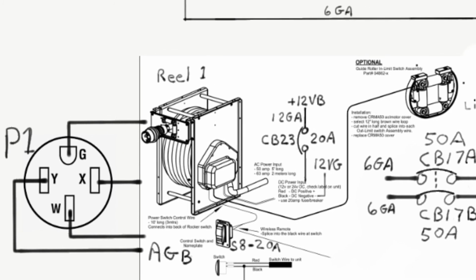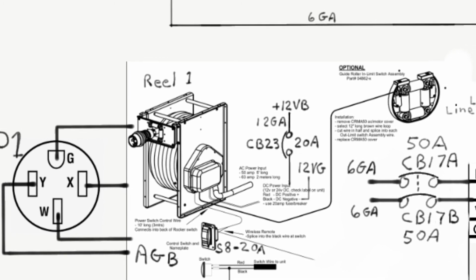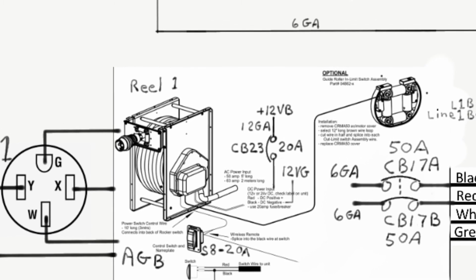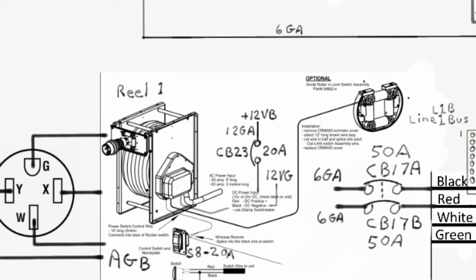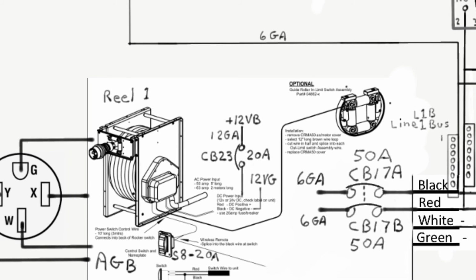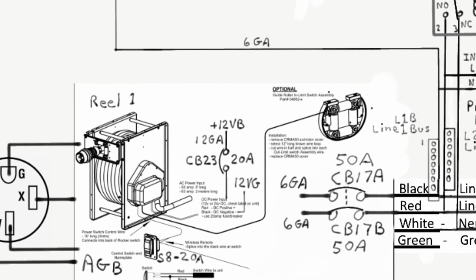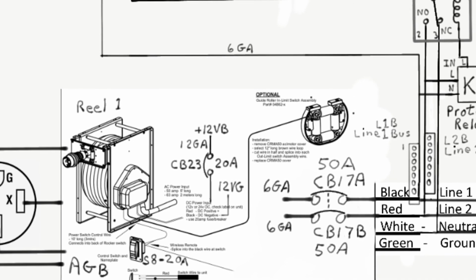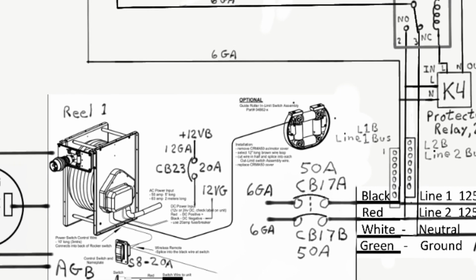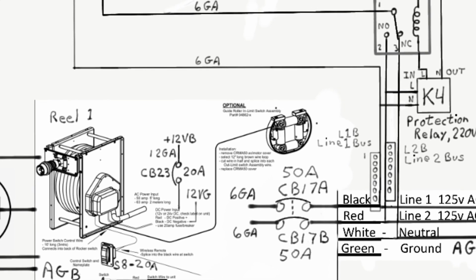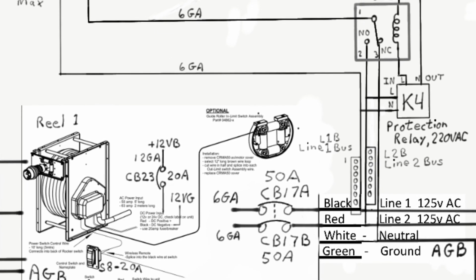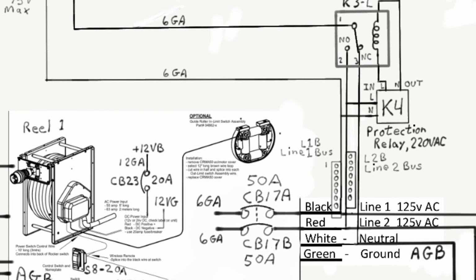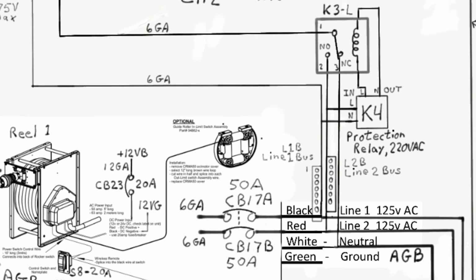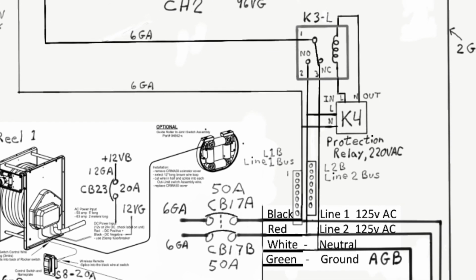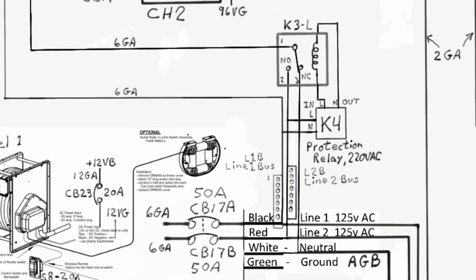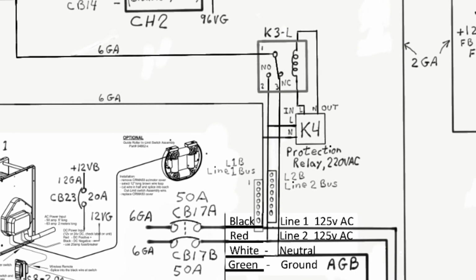And what I'm getting to is the logic of this circuit. The problem is with North America standards, you have two 125 volt or 120 volt legs, which equals 220 - I guess I downscaled a little bit. But I've created two buses here, and that bus goes into this logic circuit. The protection relay determines whether I have 220 volts, and if it does, it energizes this relay, which allows me to introduce true 220 volt voltage into the system. If it doesn't, it's only 125 volt I can charge with at 30 amps.